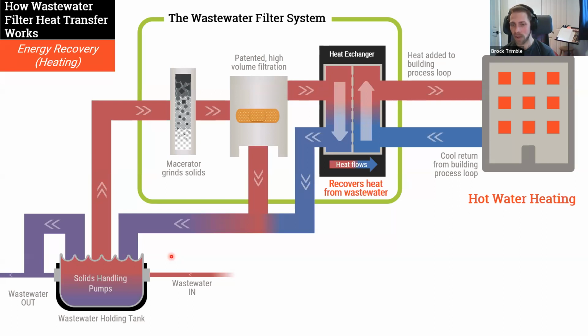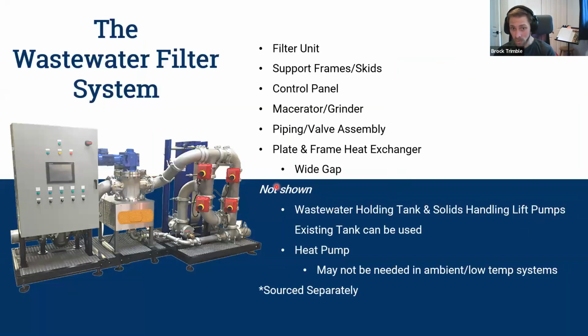Whereas this type of application filters the solids, gets rid of them, and also uses what I've shown here, these backflushing valves. As wastewater is flowing through the system, you can automatically backflush the heat exchanger anytime you start to see a delta T increase or decrease, or if you're seeing pressure differentials change from design. That keeps the wastewater heat exchanger, which is a very specialized wide gap design, passing any small particulate through, with no chance of clogging or degradation. By backflushing, it ensures the system stays clean. Any minor buildups are blown off and sent back to the city sewer, and you maintain the overall flow rate and thermal transfer that you're looking for over the lifespan of the equipment.